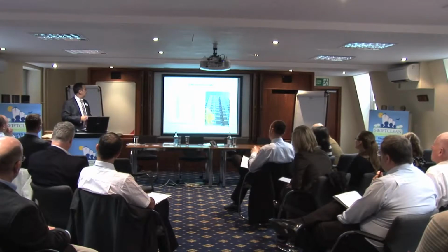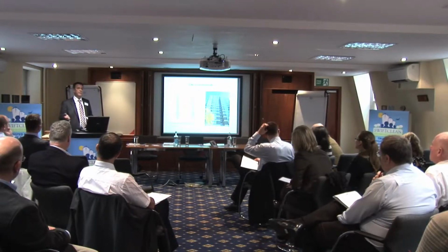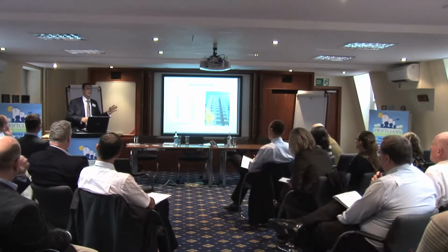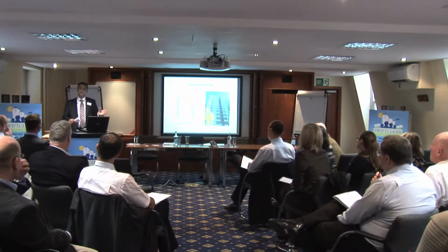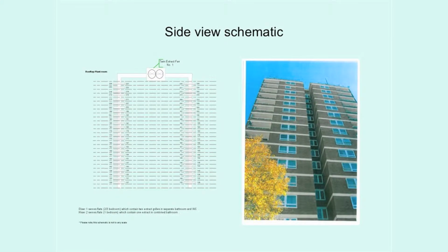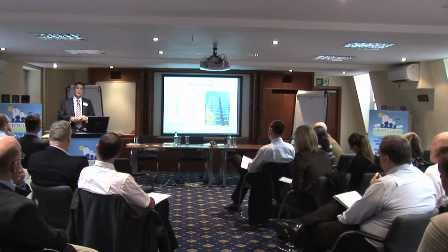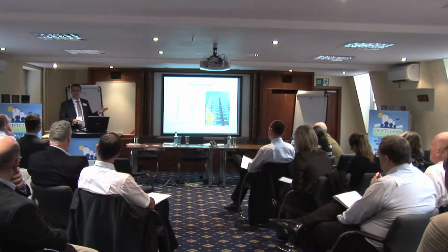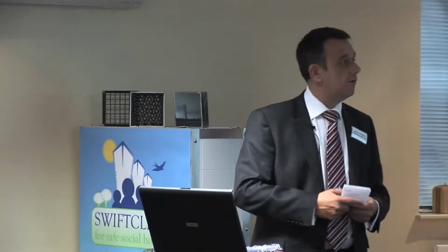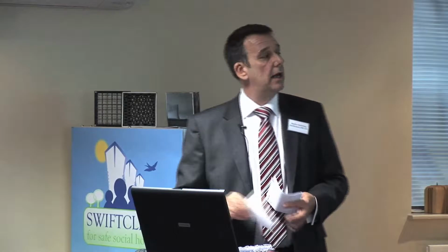90% of the blocks that we get asked to look at have never been cleaned before. They might have had a cosmetic grill clean or a grill change, and maybe the little shunt ducts, the little lines you can see going across, have had an attempted clean, but very rarely do we get asked to go and look at a block where we've actually seen it's been cleaned from top to bottom. The fans need overhauling. Some of these fans are 40 years old. They may not have the original bearings and belts, but the actual fans themselves are that old, and some of them now are not actually efficient enough to draw out.